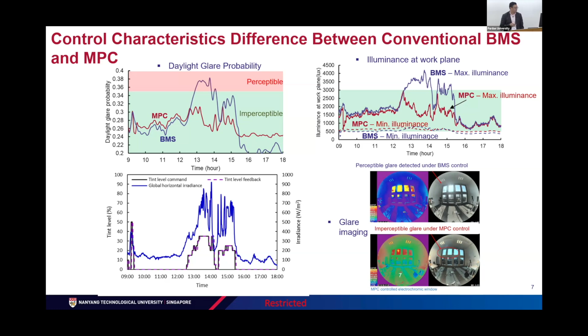and using the tint level of the shading system, we can actively control the amount of daylight coming into the building. So when we measure daylight glare probability in Singapore, the constraint is that the DGP should be within 0.35. As you can see, the typical BMS is not able to constrain within this 0.35 of DGP. Similarly, if you look at the illuminance level inside the room, the typical allowable constraint in Singapore is that illuminance should be within 500 to 3000 lux, but as you can see, BMS often violates that constraint. So MPC is able to maintain within these constraints.